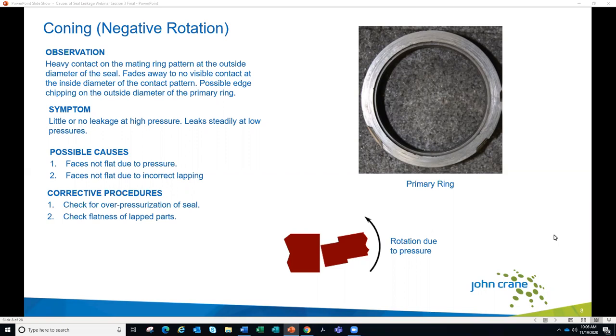On the mating ring, we would only see heavier contact at the OD of the wear pattern. This can be caused by pressure — when it's in an OD pressurized arrangement, the pressure is going to cause the primary ring to rotate and distort inward. The other thing that could happen is that the faces may not have been lapped correctly — they may have been improperly lapped with a higher surface at the OD, which could also cause this.